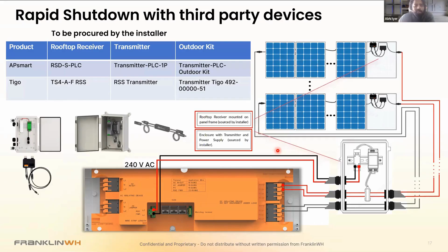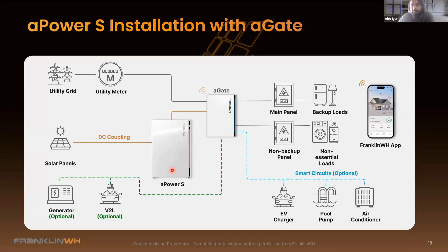With all that said, this is what we believe an average aPower S install is going to look like. PV lands on the aPower S, which lands on the ESS breaker on the aGate, rated for 60 amps. The aPower S, with 10 kW and 11.5 kW continuous, needs to be landed on a 60 amp breaker. This combination is built for whole home backup, but you also have the ability to do partial home backup, a critical loads panel, or non-essential loads. So you have a lot of flexibility with the aGate, whether it's whole home, partial home, or load management.